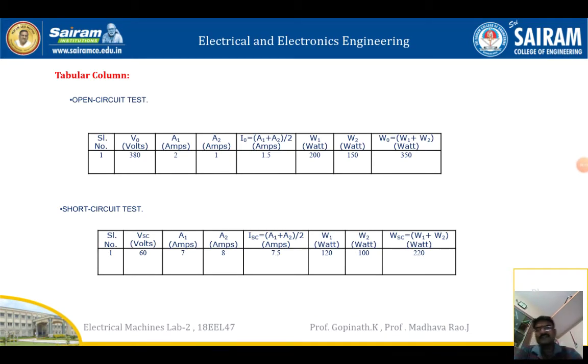In the open circuit test we get 380 volts as the supply voltage, the current will be in the range of 1 amp to 2 amps, and the corresponding power will be about 200 watts. For the short circuit test we get more current and the voltage will be very low, the ratings being at 60 or 70 volts.